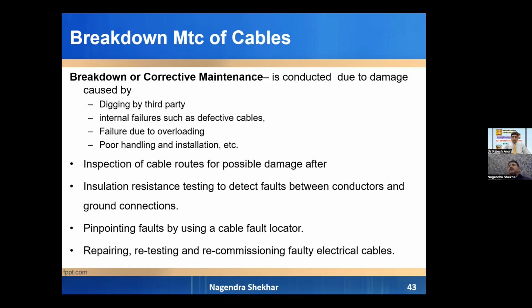Poor handling and installation: while laying cable, it is not handled properly, not laid properly. We haven't used proper mechanisms like pulleys. We just laid these cables without proper arrangement. So how to put it into operation? First of all, inspect the cable routes for possible damages. We have to conduct tests and find out the fault if it is underground. We have to pinpoint the fault through CFLs or cable fault locators, then repair, retest and recommission the faulty cable. That is breakdown maintenance.